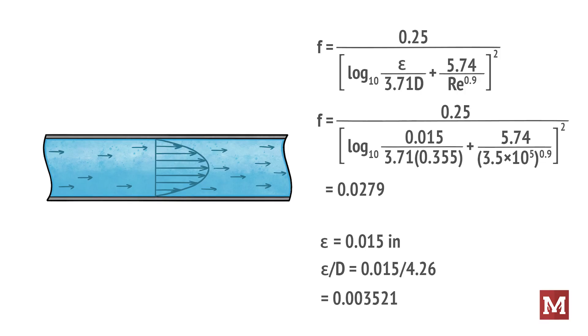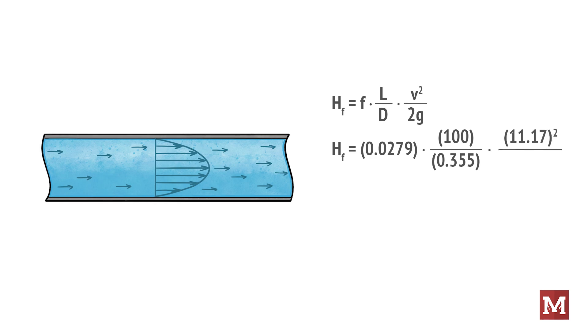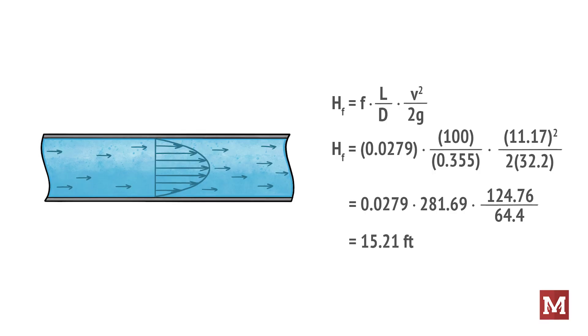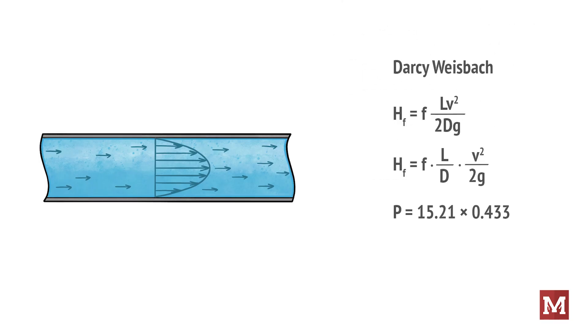Now we can calculate the pressure loss in terms of feet of head by plugging all that in. So H sub f is going to equal 0.0279 times the ratio of the length 100 feet divided by the inner diameter 0.355 times the velocity 11.17 squared divided by twice the gravitational constant. From that we get an answer of 15.21 feet of head. So to make the comparison with what we arrived at with the Hazen-Williams equation let's convert that to PSIG. And the easiest way to do that is simply multiply by 0.433 which gives us 6.59 PSIG.